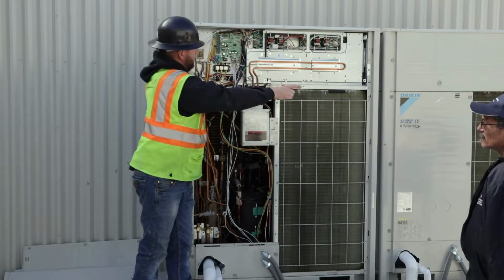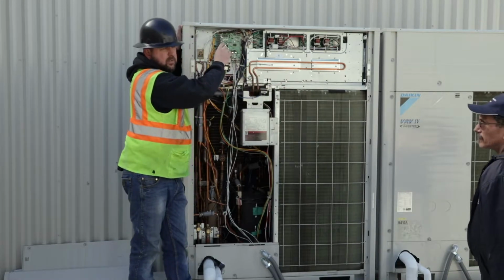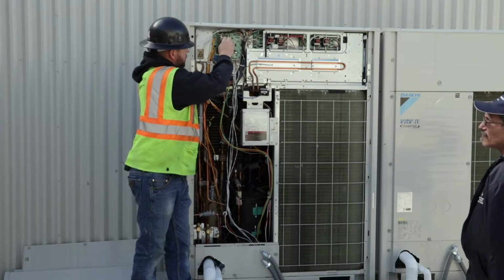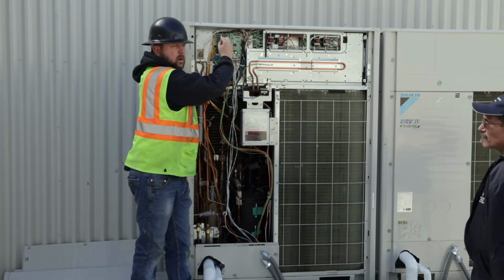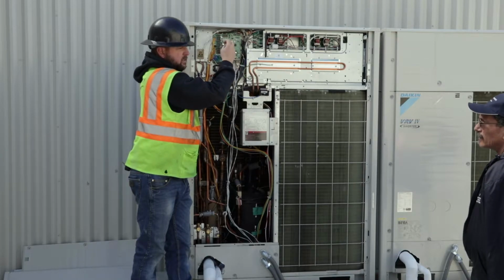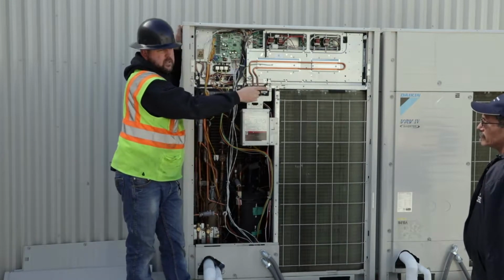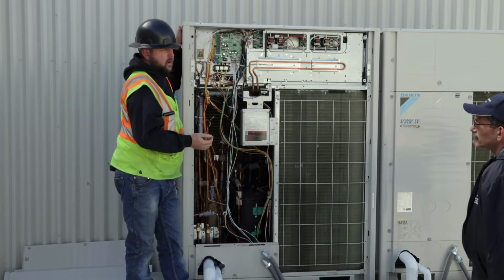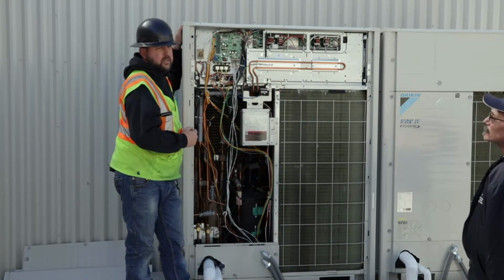If your slave goes down, you go back to mode 39, and after you set it, 0 will pop up, 1 is for master, you hit set again, 2 will be for your slave. So that's one way of doing it, but it's only temporary. It's only for 24 hours.